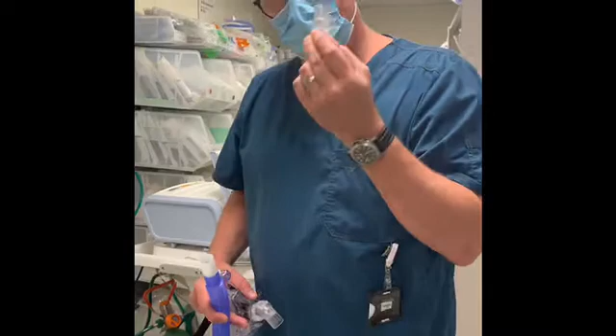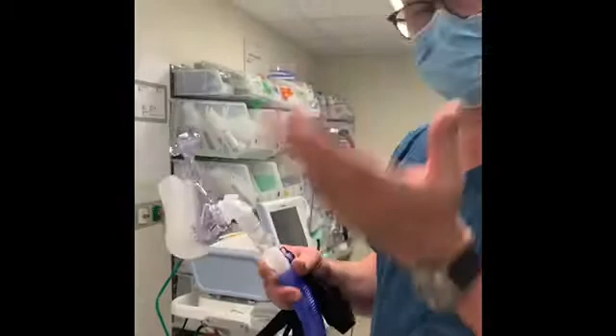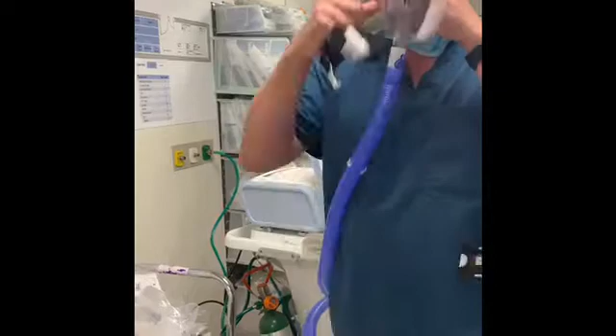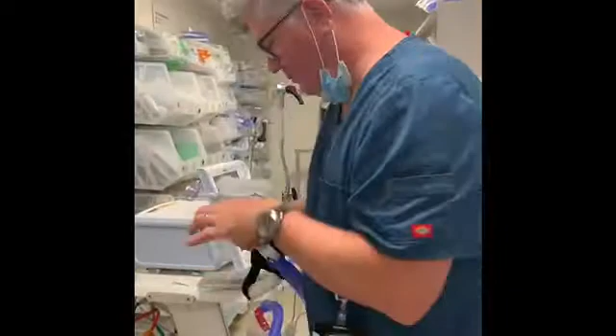So in the RT219 also, there is a valve here. This is called a passive exhalation valve, and it goes between the tubing and the BiPAP mask. What this does is it allows CO2 to passively be exhaled, so a person's CO2 doesn't rise. So when the mask is on and they're breathing in and out, the CO2 comes out passively through here.